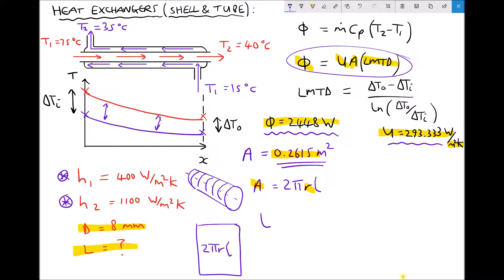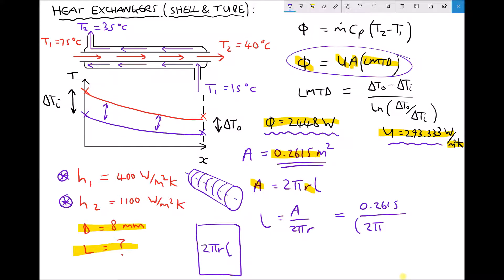Rearranging for L, we get L equals area divided by 2πr. Plugging in the values: area is 0.2615, divided by 2π times the radius. With a diameter of 8 millimeters, the radius is 4 millimeters, or 0.004 meters. Plugging those values into the calculator gives us a length of heat exchanger tube equal to 10.40 meters.